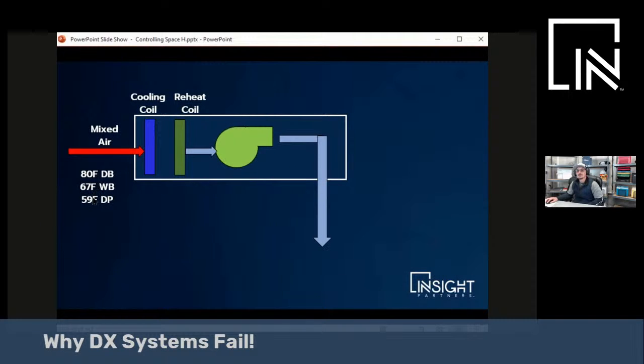You've got 80-67 entering your coil again. And to dehumidify the air, we're in dehum mode. Typically, you're at full capacity on your cooling coils. So the cooling coil is at full capacity, and you are dehumidifying and cooling the air as much as you can. Now if you blow 52 degree air into your space on a day that's not design day, you're going to probably cool everybody out. So what we do is we reheat.